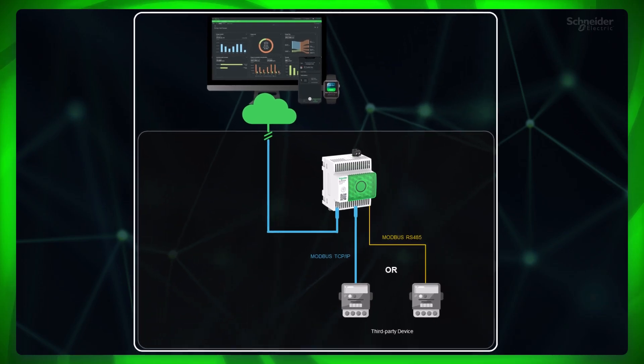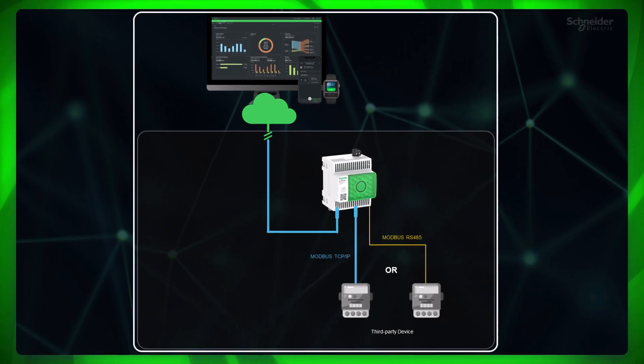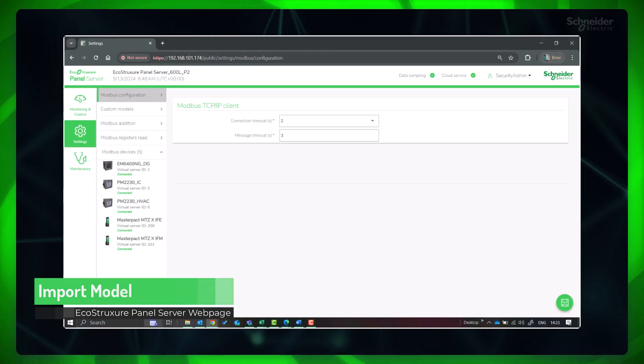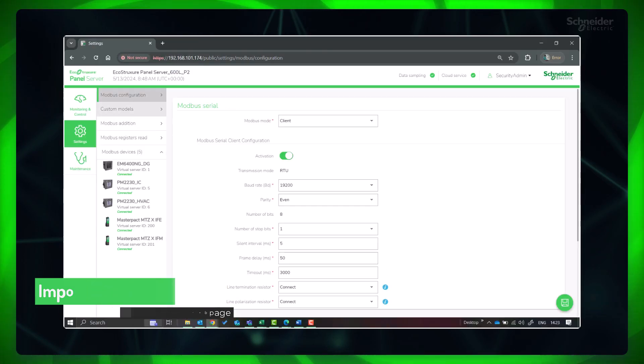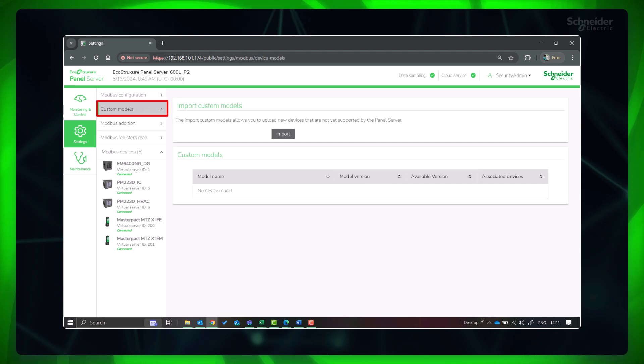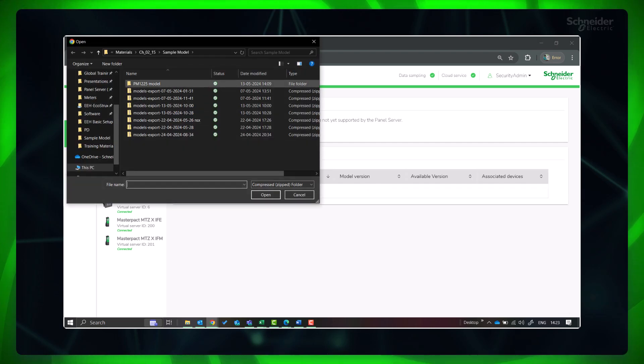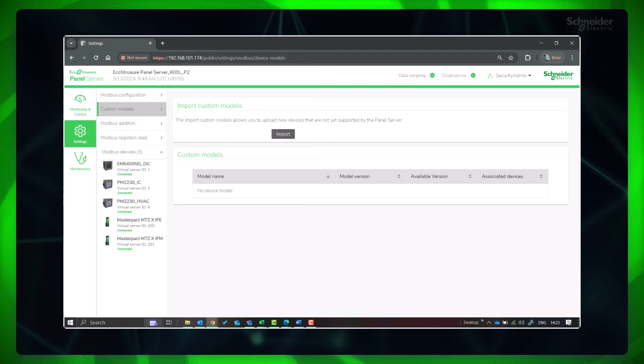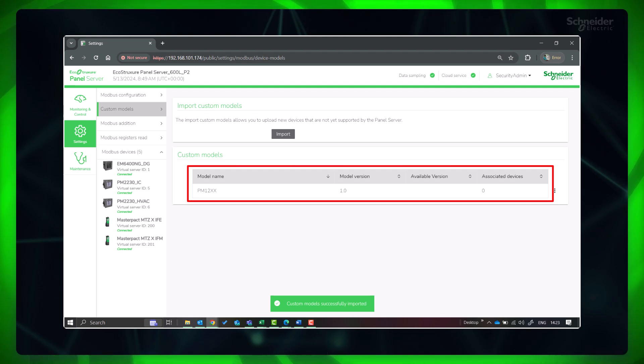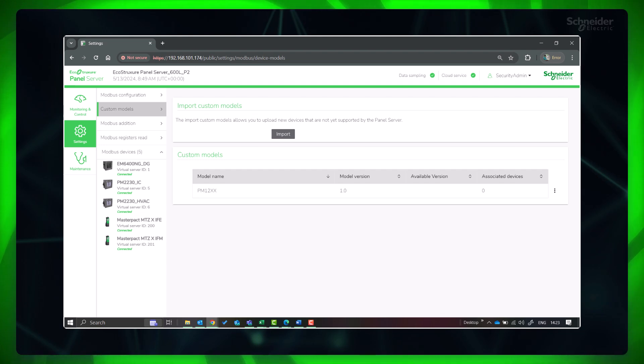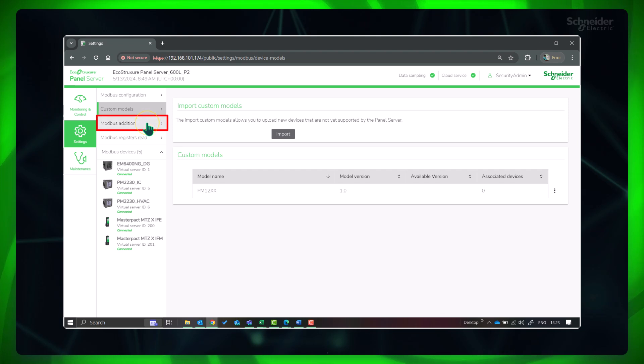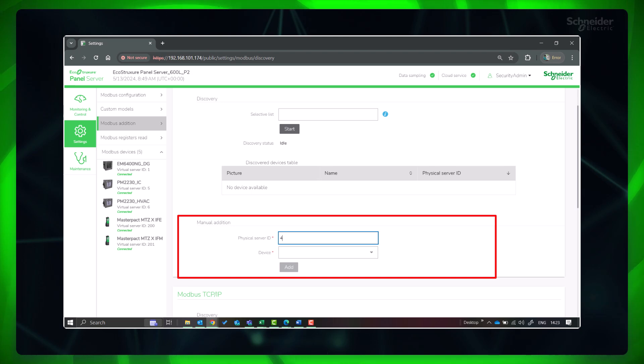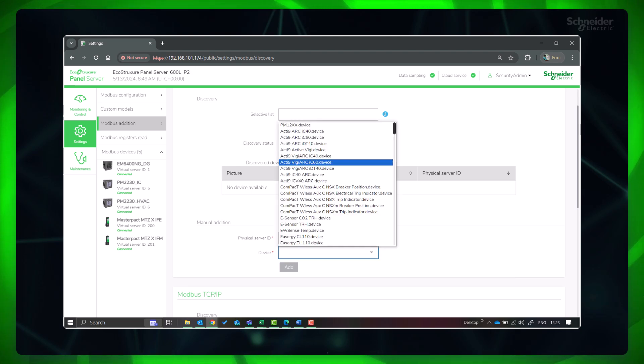Please make sure the third-party Modbus device is properly wired and connected to Panel Server. Go to the Panel Server web page, then Modbus Devices, then Custom Models, and click Import. Select the already exported model from EcoStruxure Power Commission web portal. It will show up with the version. Now let's add the third-party device and assign this custom model. Provide the Modbus slave ID of the device, select the custom model from the dropdown menu, and click Add.